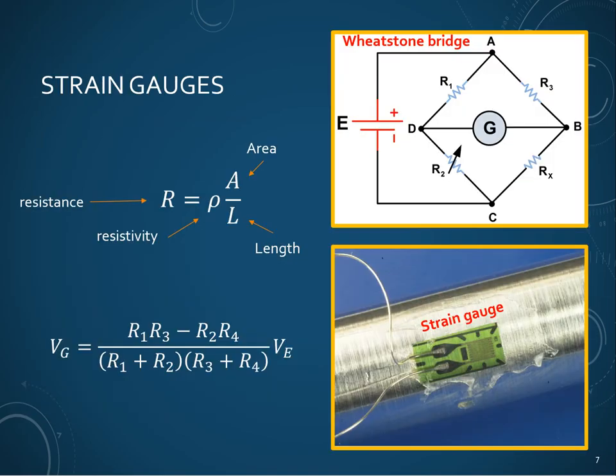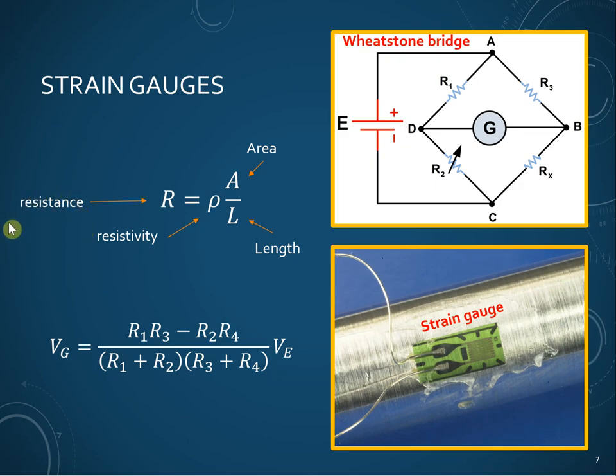Another commonly used sensor device is a strain gauge, which is usually used to measure compression and elongation. Strain gauges are essentially long wires that are stretched and whose resistance changes. The resistance of a material is a function of its resistivity, which is a material property, as well as its area and length. Whenever you elongate a wire, you're changing its length and also its area — the area gets smaller due to the Poisson ratio — and because of that the resistance changes. This change in resistance is often quite small, so we create a device called the Wheatstone bridge, comprised of multiple resistors and a strain gauge.